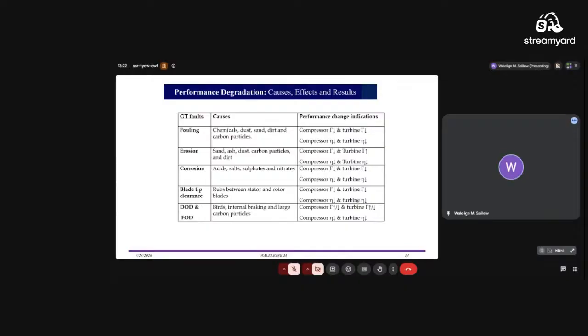The causes, as I described in the previous slides, lead to performance change. If fouling happens in the gas turbine, the flow capacity in the compressor and turbine will reduce, and the isentropic efficiency as well will reduce. Erosion has the same effect as well. But in the compressor, the flow capacity will reduce, while in the turbine, it increases the flow capacity. The efficiency will reduce on both the compressor and turbine side. Corrosion has the same effect as fouling. Blade clearance, same.